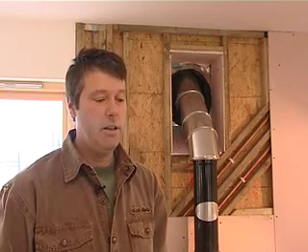So we got most of our most useful information, I suppose, from the solar companies, who were right up there with the whole thing about using thermal stores with the coils that run through, and that was how we managed to blend the system: every part of the system has its own coil, and then it's all feeding into the same sink of water, and that's how you make it work. You can have open vented systems and closed systems, pressurized systems, running side by side without any trouble.